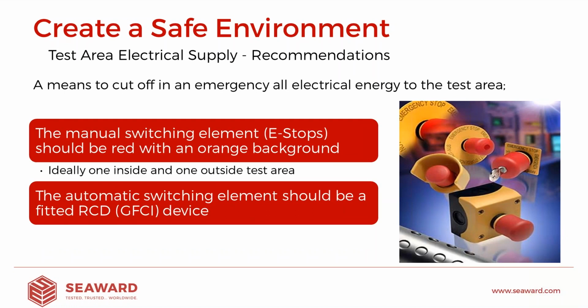Finally, let's discuss the electrical supply for the test area itself. We should certainly include methods of disconnecting the voltage from the entire area in the event that something was to go wrong. And there are two things we can look to install to do that. The first one is what we call emergency stops. You'll see them in the image on screen. They're generally a big red button with either an orange or a yellow background, so there's a good high contrast against maybe the walls. So they're easy to spot, easy to find in the event that someone needs to hit the off switch.